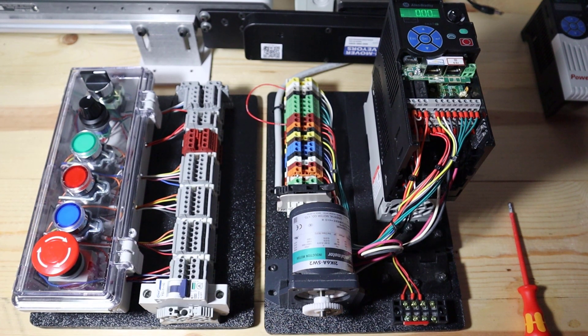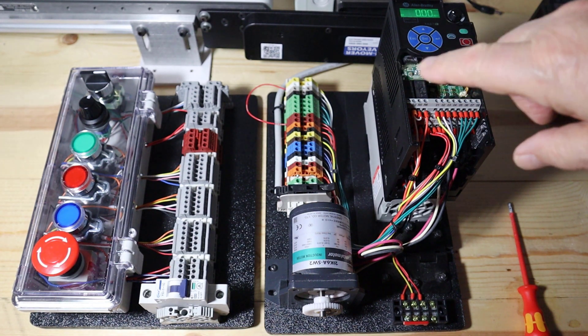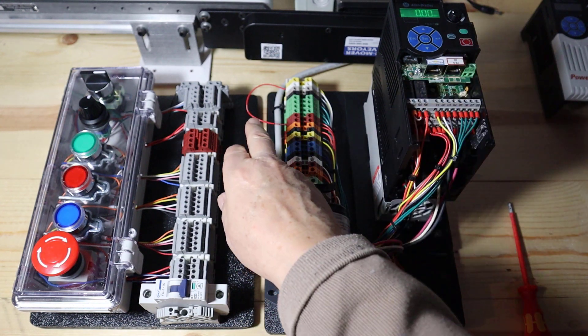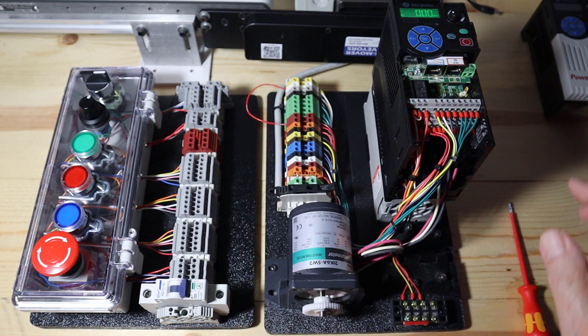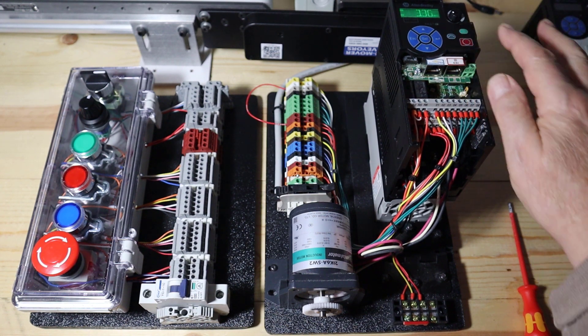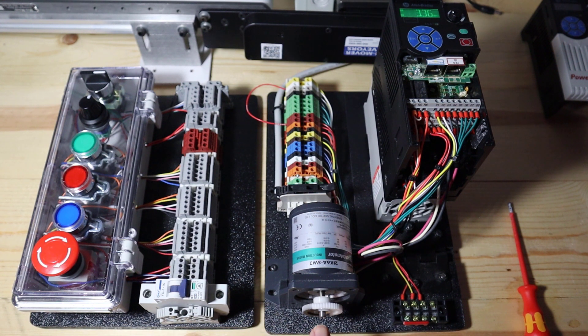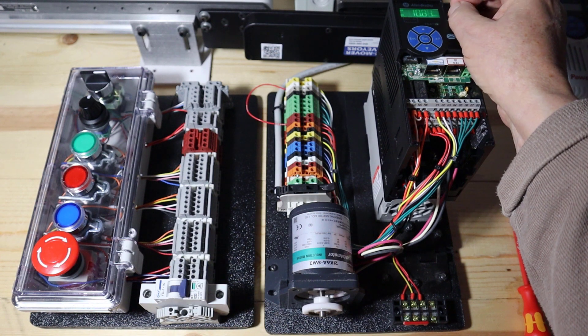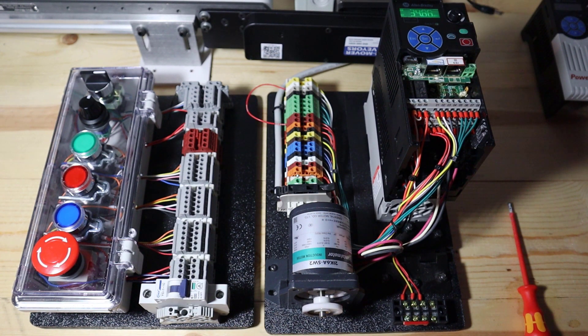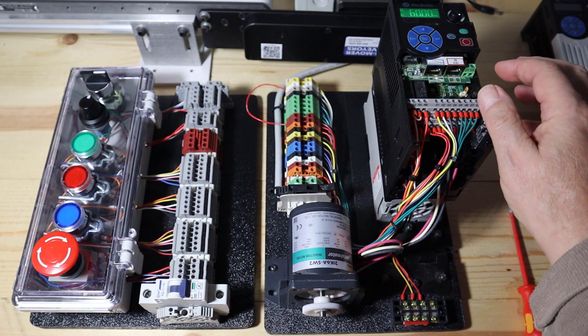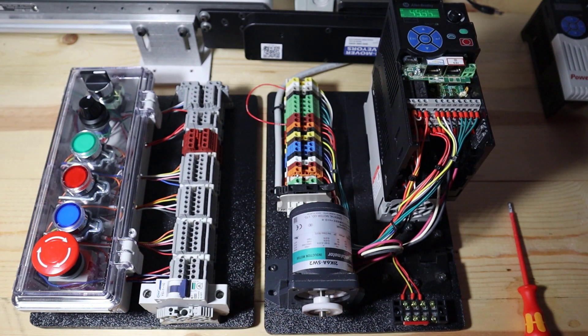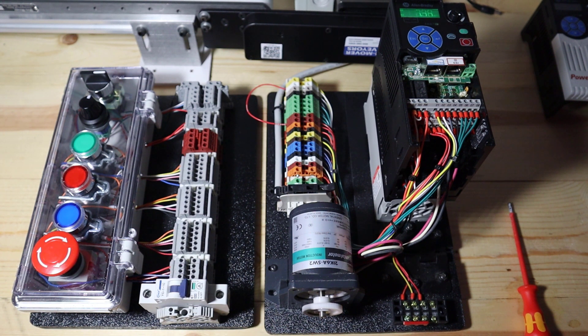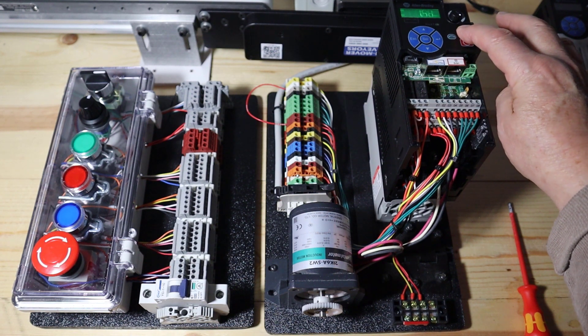One of these you can see is a common, we have two terminals there jumpered together with a yellow wire and it runs down here to the center terminal, then we have this jumper in here that we can pop out and wire in e-stops and other circuitry. The first thing I want to demonstrate, and I apologize for the camera wiggling, it's on a boom and if I touch it it sits there and oscillates for a bit. First thing I want to demonstrate is that we are in the default mode for this drive and because this jumper is still in here, this red wire up here, if I hit the green button the drive starts driving this motor right here.